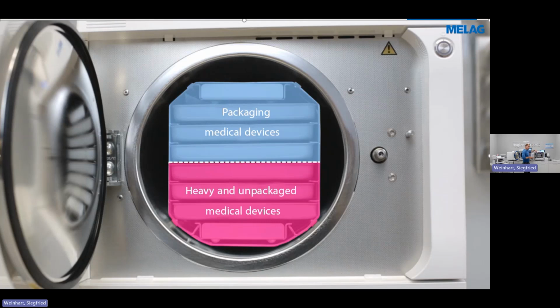So always try to correctly load the sterilizer yourself as well. Always be aware you can put mixed loads in there. Just because it says it's a vacuum autoclave and it's for pouched instruments, it doesn't necessarily have to just be a full load of pouched instruments. You can use that unit to put other instruments.